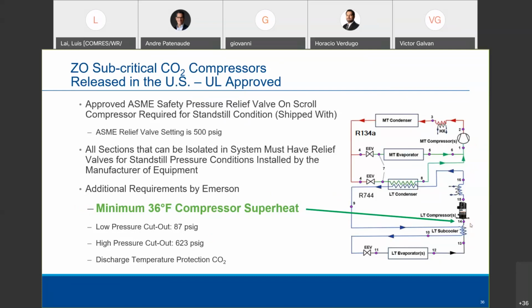CO2's properties are a little bit different than your normal HFC. And I know we're Copeland people, we've always said, hey, if you got 20 degrees superheat at the inlet of your compressor, you're good to go. And you are for medium temp. This happens to show a cascade system. I apologize, this is a cascade where you've got 134A on the primary and CO2 on the secondary. But my point here is low temp CO2 application, regardless if it's a booster or a cascade system, you need 36 degrees.